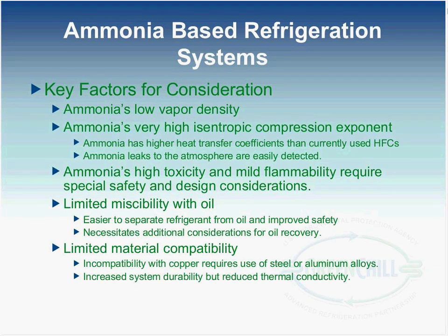Ammonia has a very high heat transfer coefficient because of its favorable specific heat, thermal conductivity, and viscosity parameters. Ammonia is easily detected. You don't need a leak detector. It is alarming. At a concentration of 5 to 50 ppm, you sense it. You will know that it is leaking. And ammonia is definitely toxic and flammable. It is categorized as a B2 group refrigerant, and you would require special safety and design considerations. The industry is used to it, and there is proven technology to take care of those things.